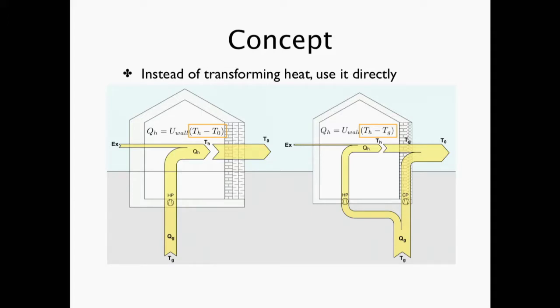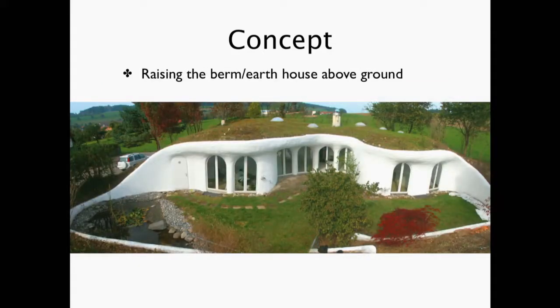So why don't we split that up? We can still drive the heat pump, but also minimize the temperature difference across the wall by putting this layer of pipes in the wall—in essence creating an effect where the wall feels like it's underground. So we bring that bermed house or earthen house effect, which has very high thermal performance, and raise it up by piping that underground heat into the facade.